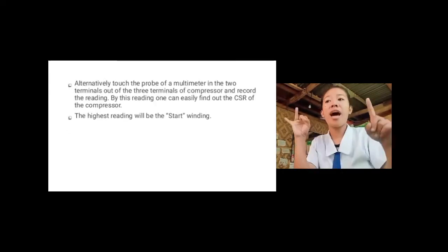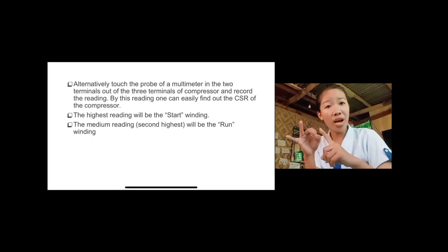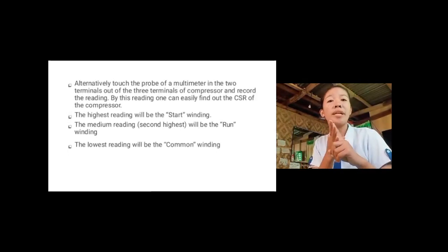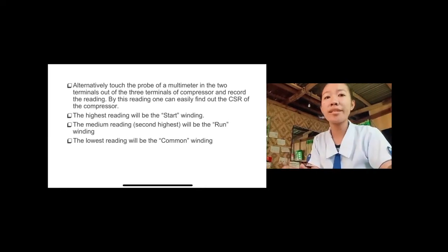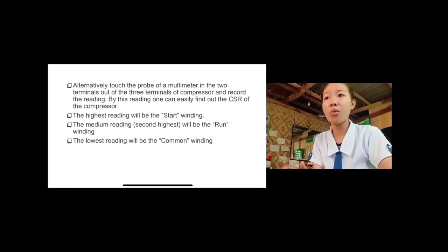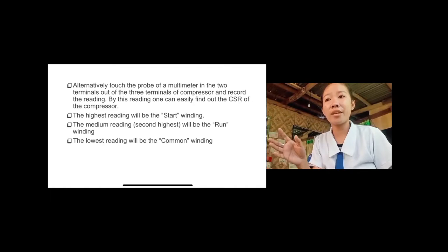So the highest reading will be the start, the medium reading, or the second to the highest, will be the run winding, and the lowest reading will be the common winding. As you can see in the illustration below, this is a common example of the CSR.